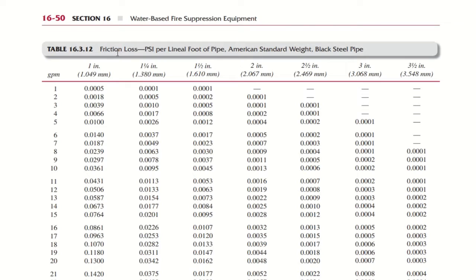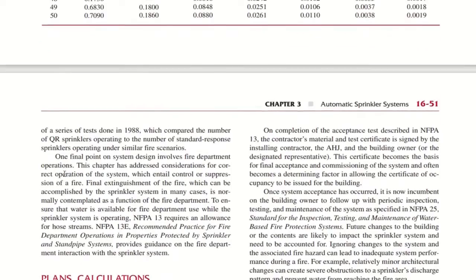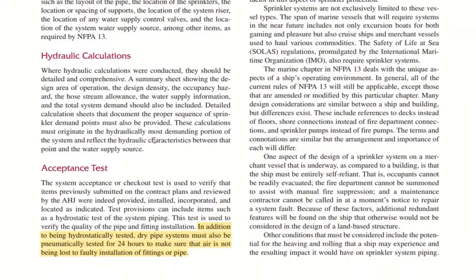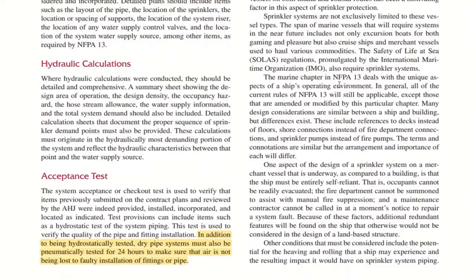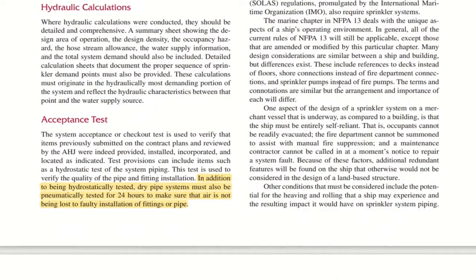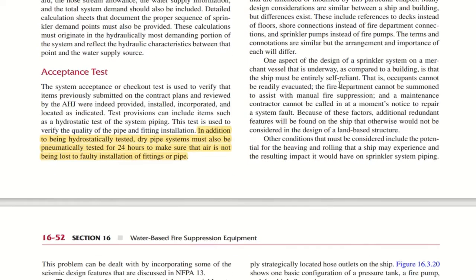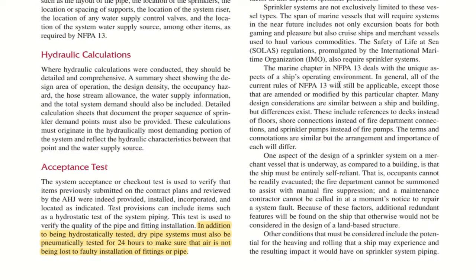And also finally we have gone through the friction loss shown here based on the pipe size for black steel pipe and the GPM. And marine applications also, they are using special type of sprinklers. Marine systems are covered in the other NFPA codes.